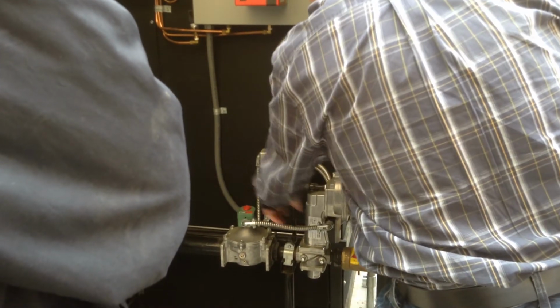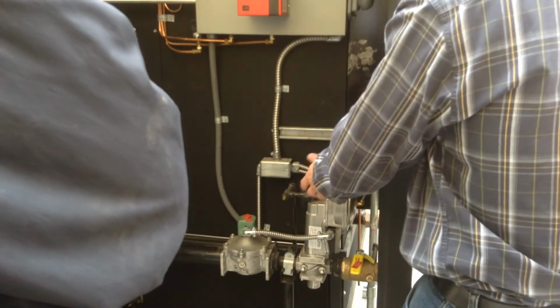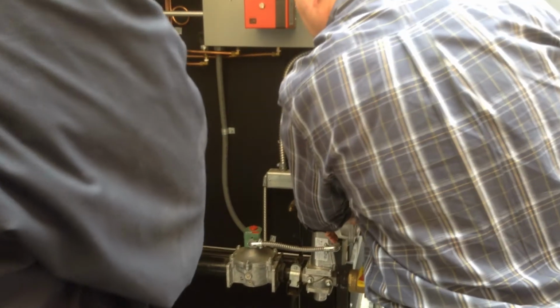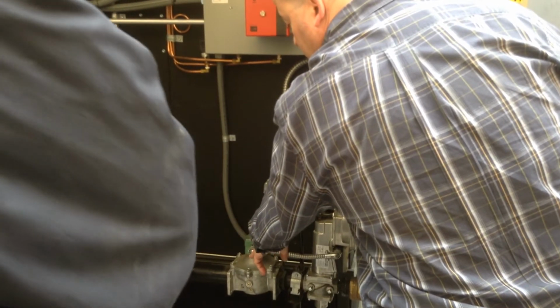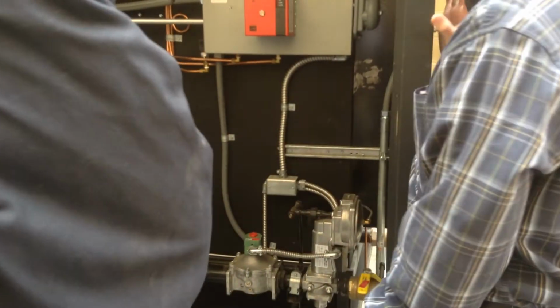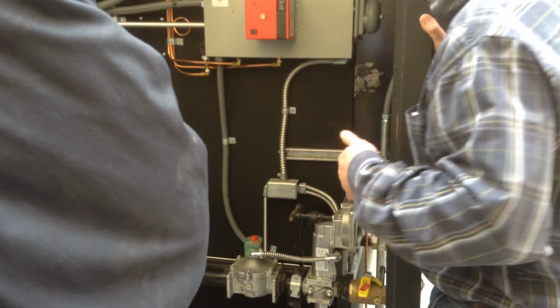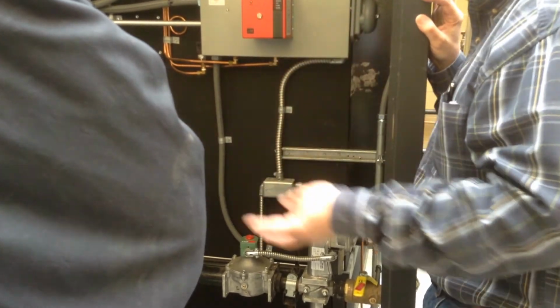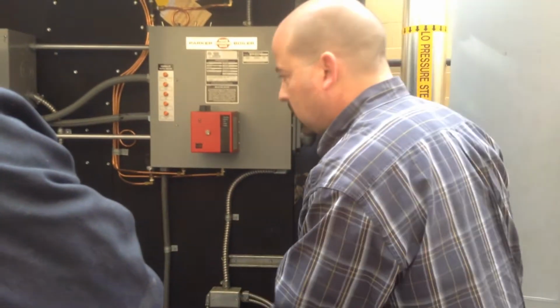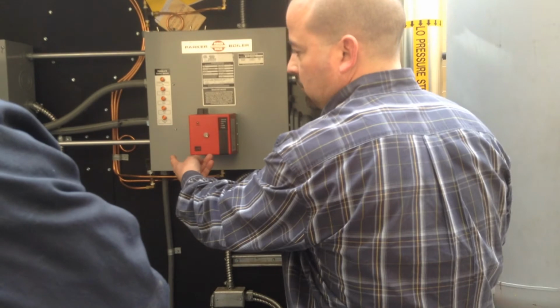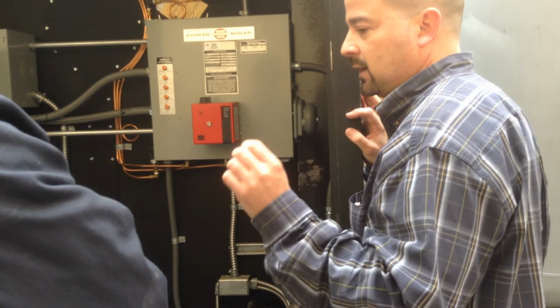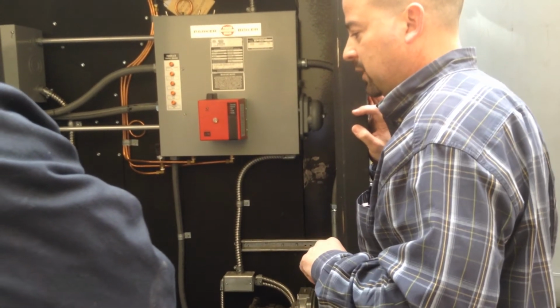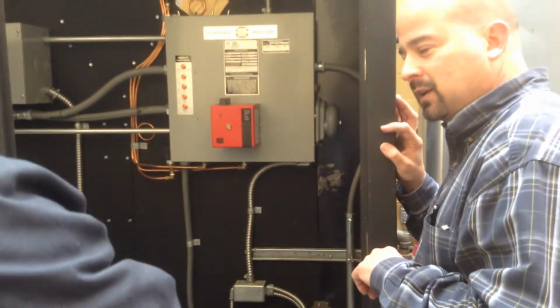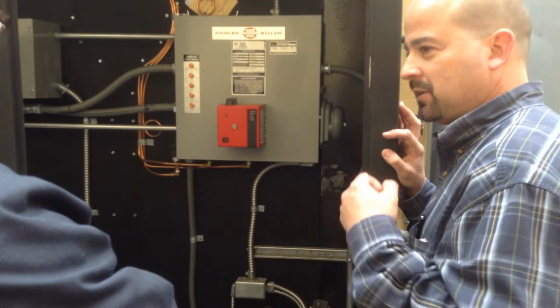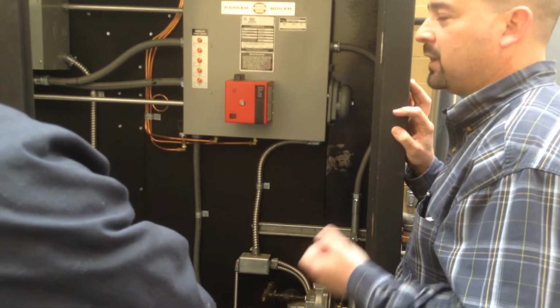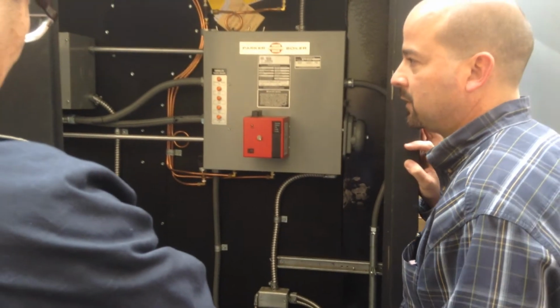And then your main gas train consists of the SKP, they call it, the Siemens, and it has a secondary solenoid valve. I don't know if you guys know this, but the reason you have two is because we're in California. California requires two of everything: 2 low water cutoffs, 2 main gas valves, 2 pressure controls. There's a code called Title 8, fired pressure vessels. Because boilers used to blow up prior to 1950, they implemented this code that said, no, we're going to have redundancy all over the place. So that's why we have 2 of everything in California.